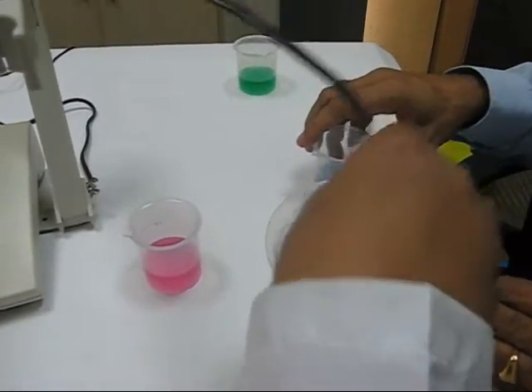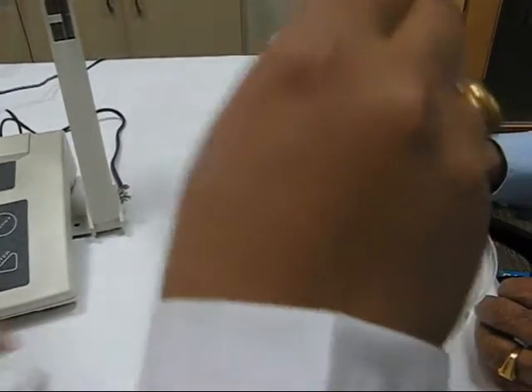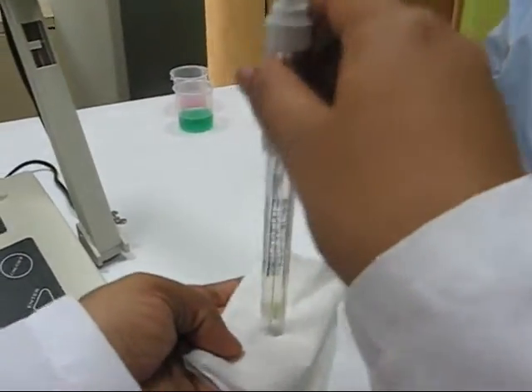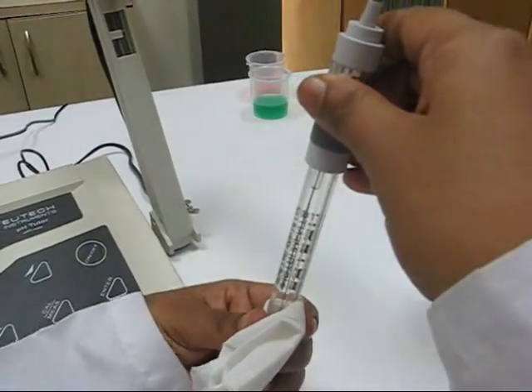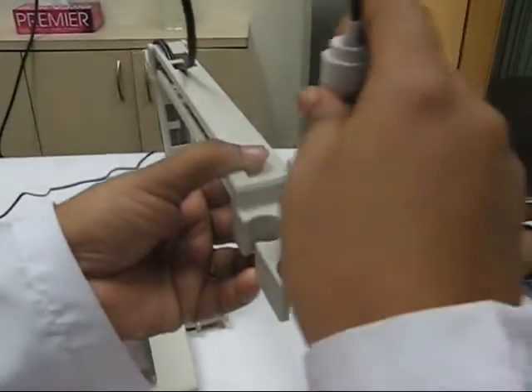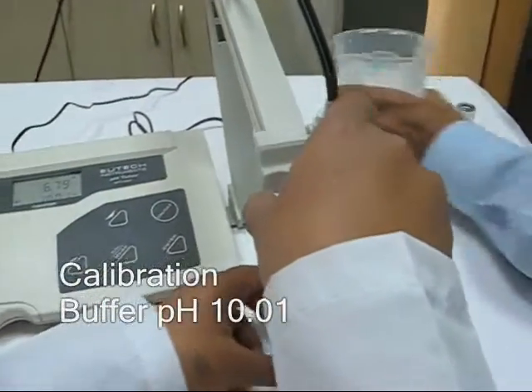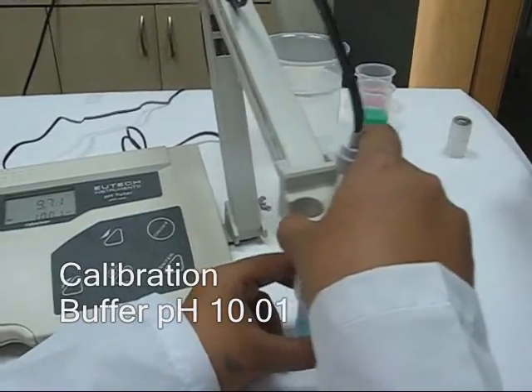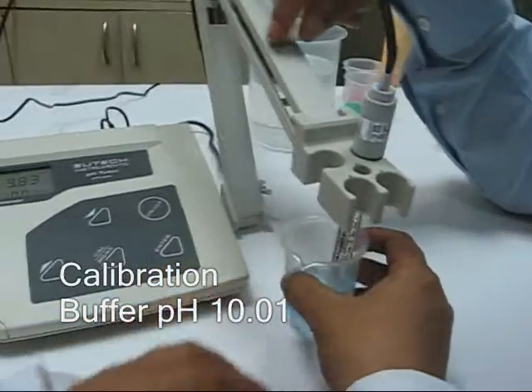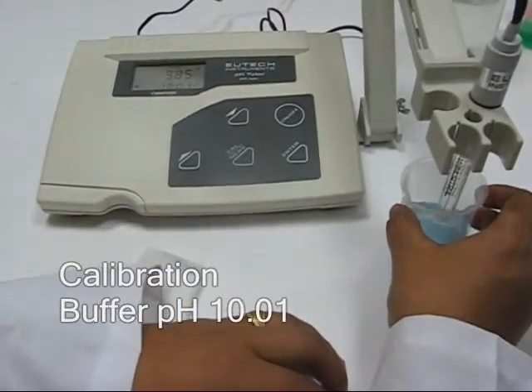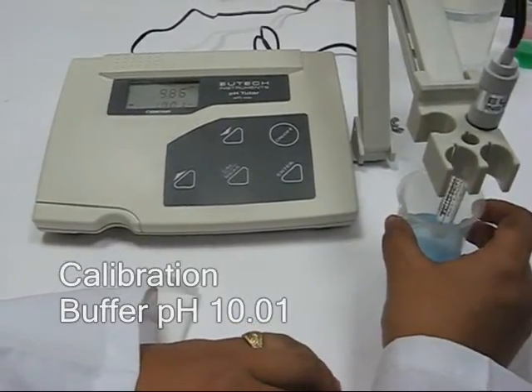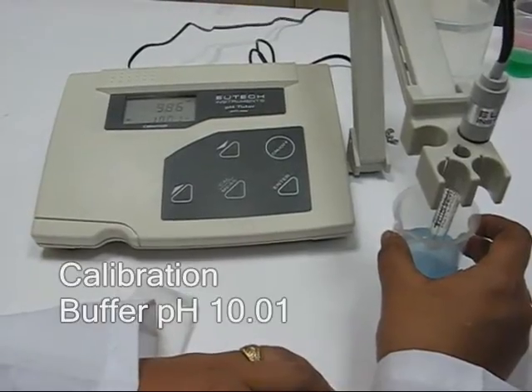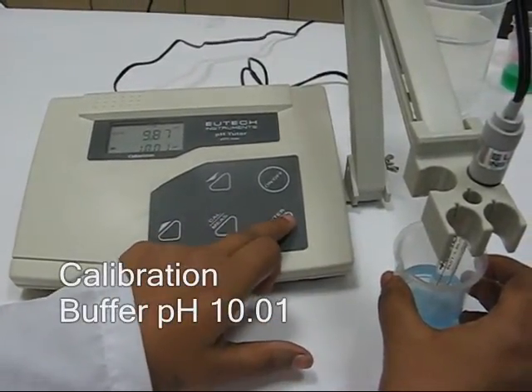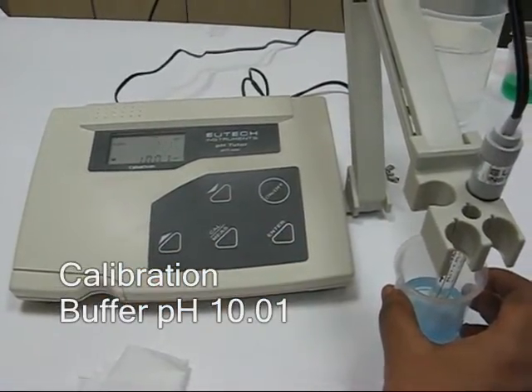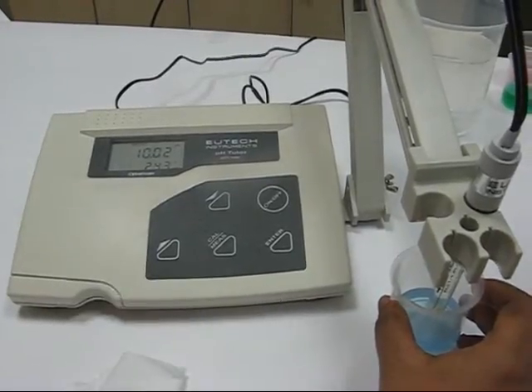Washing the electrode again. Cleaning it dry. Dab it nicely. Clean it dry. And place it back in the stand to get ready for the third point calibration. Once the reading stabilizes, you can press the enter key, and that will confirm the third point cal, and you will notice that the instrument goes into the measurement mode.